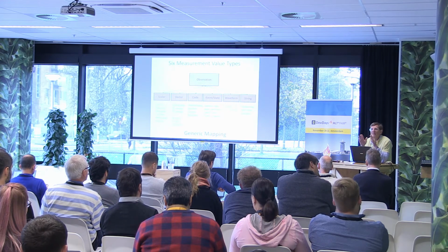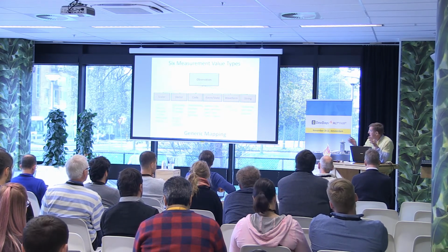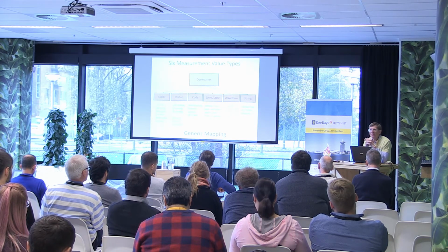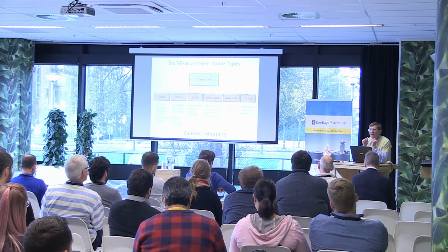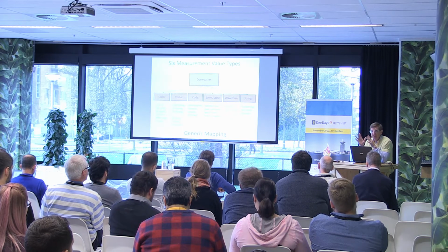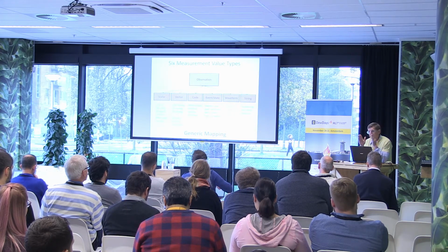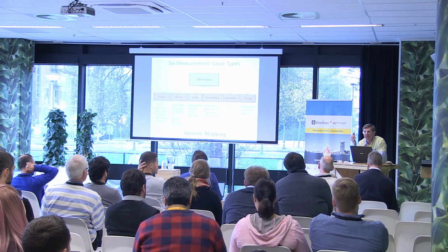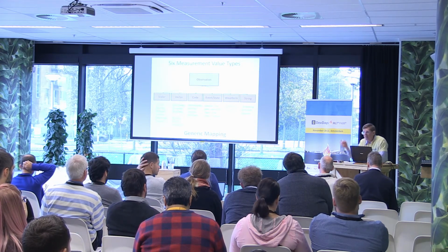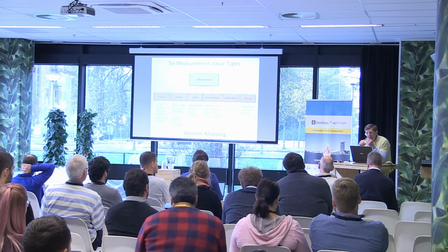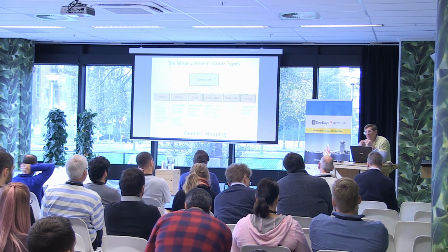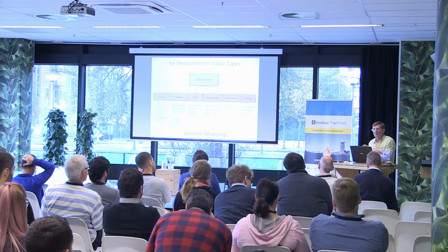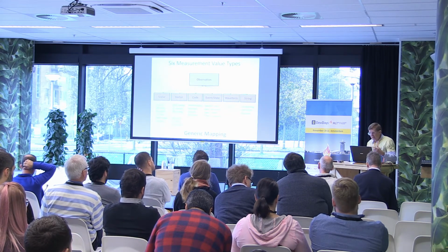But when you design the standard, we use these event state type of situations when the event states can happen simultaneously. So you get a battery low, for example, say I take this pulse ox, and the battery is low, and it can have poor signal perfusion, the finger might not be in right, and all of those happen simultaneously. Like a vector of codes.